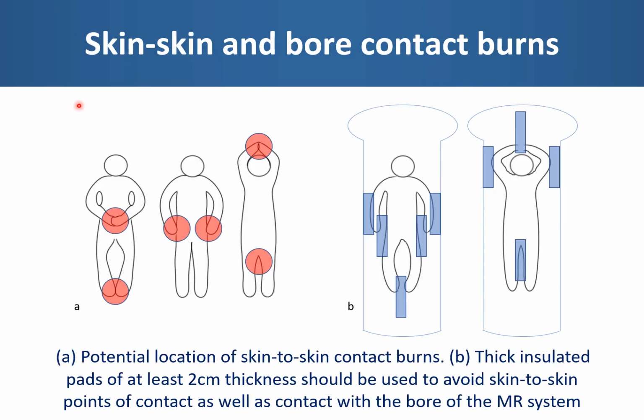RF burns have been particularly noted where there is a small area of skin-to-skin contact. The burns are generally due to the limbs creating large diameter loops, and where the loop is closed, the point of greatest electrical resistance occurs. Interestingly, unlike touching a hot object, these burns are not happening at the skin surface, but in the fatty tissue immediately below the skin where there are no pain receptors. So patients could be burned, but until that burn damage has an opportunity to propagate through to the skin, there is no sensation of pain and no observable evidence of a burn.